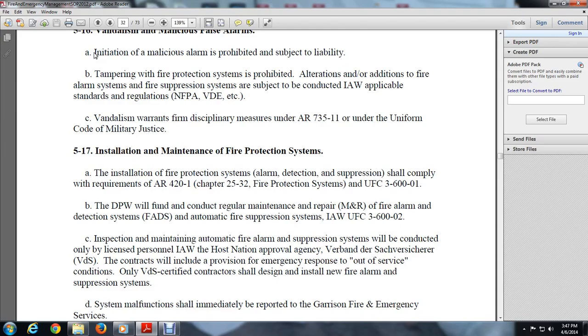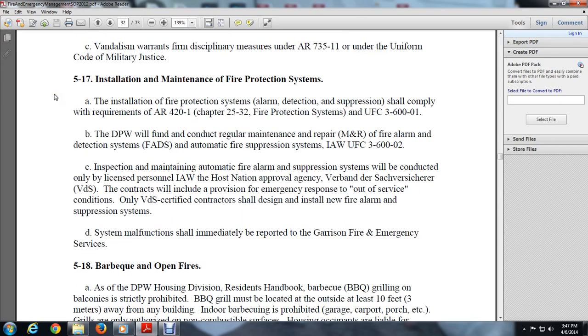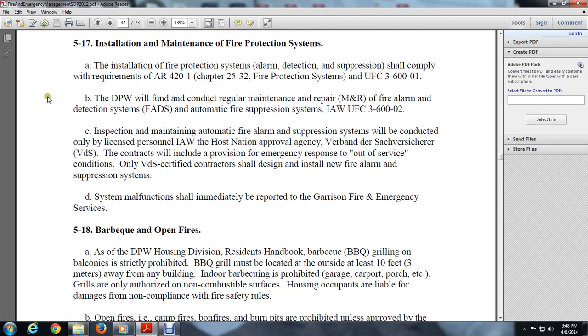517. Installation of fire protection systems. The installation of fire protection systems, including alarm, detection, and suppression, shall comply with the requirements of AR 420-1 and UFC 3-600-01, Fire Protection Engineering for Facilities. The Department of Public Works has funded and conducts regular maintenance and repair of the fire alarm detection system, FADS, and automatic fire suppression systems in accordance with UFC 3-600-02. Inspection and maintenance of automatic fire alarm and suppression systems will be conducted only by licensed personnel in accordance with host nation approval agency requirements. The contract will be approved and include provisions for emergency response to out-of-service conditions. A certified contractor shall design and install new fire alarm and suppression systems. System malfunctions shall immediately be reported to the Garrison Fire Emergency Services.